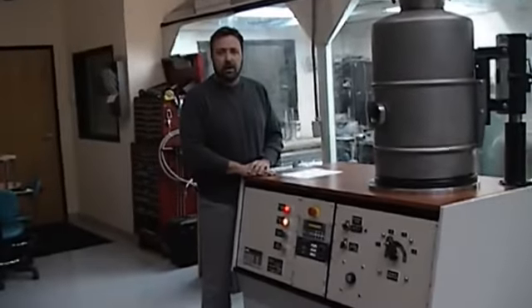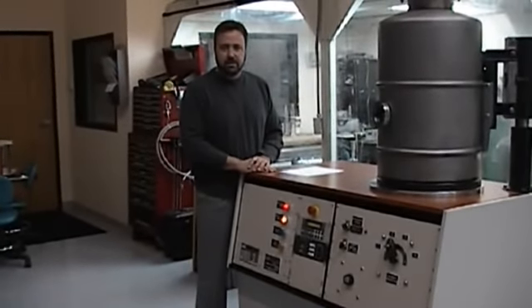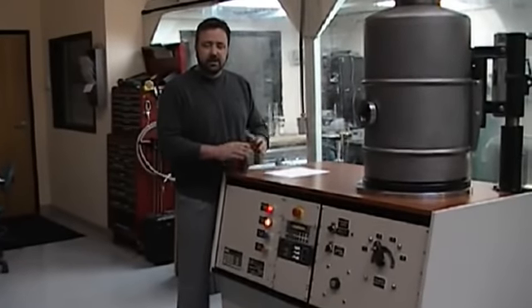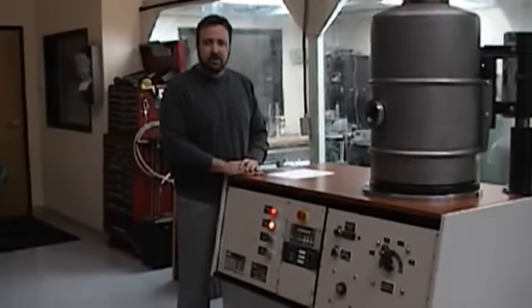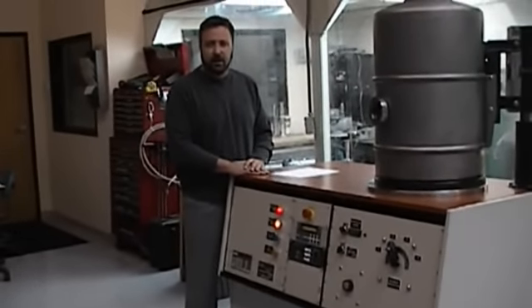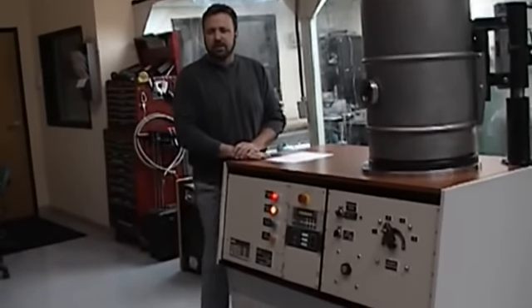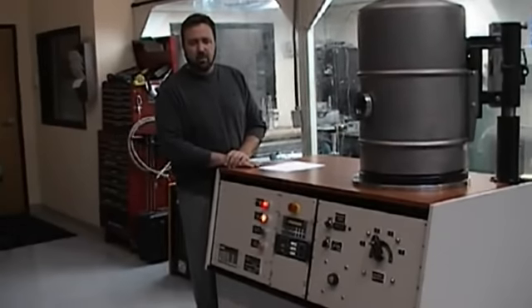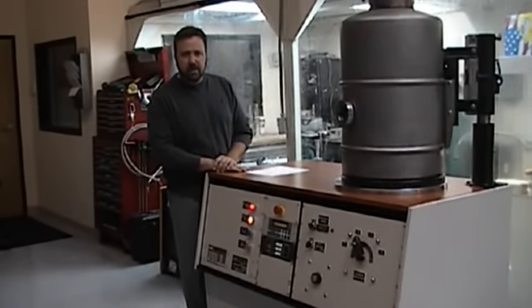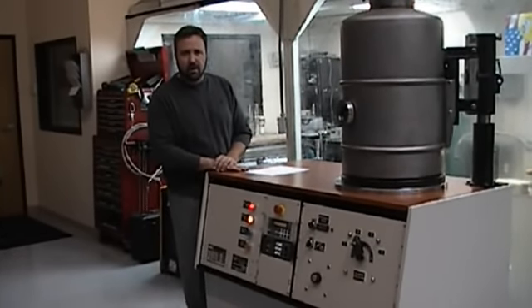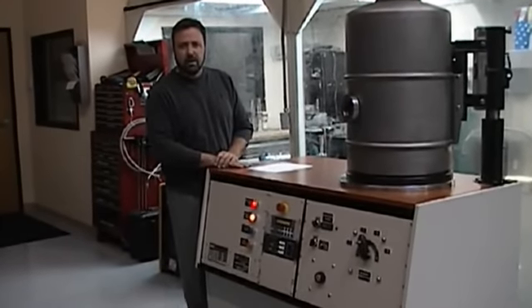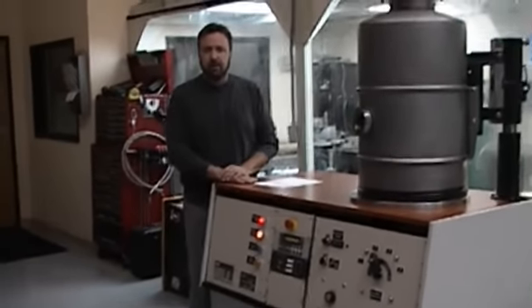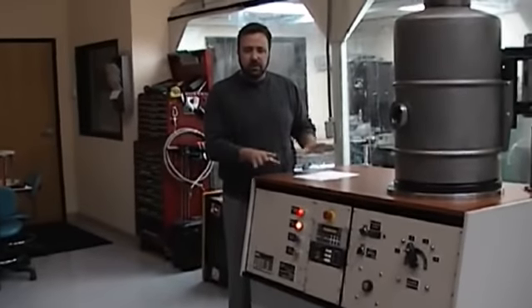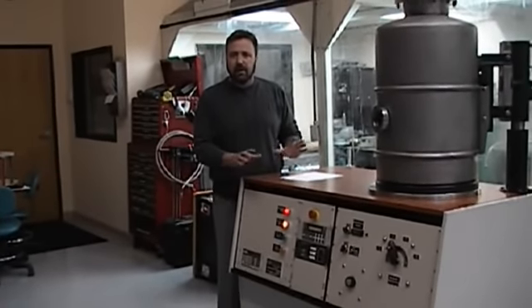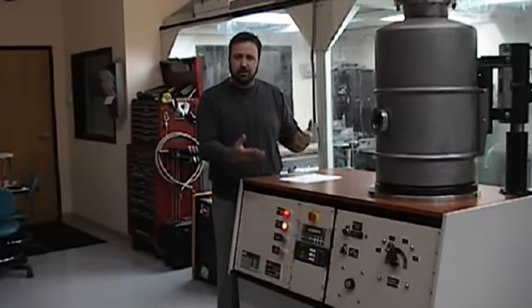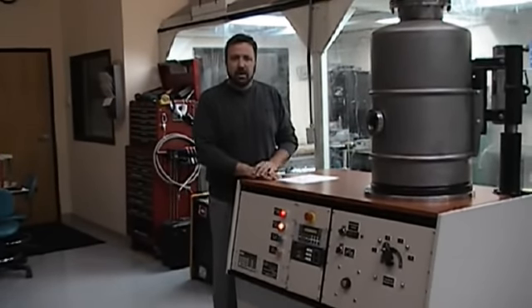Cryo pumps. Well, I got an opportunity here. The way you run your cryo pump, as I explained earlier, is it's a capture pump. It takes approximately an hour and a half to get cold, 2 hours to get cold. And when it gets cold, you're best letting it run, continue to run, if possible. That's typically the way they're designed to operate. Once they are cold, you just leave them be, go home at night, have the operator come in the morning and start the machine.